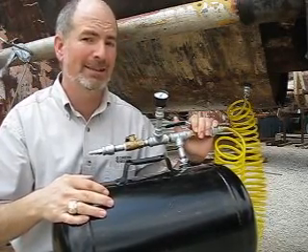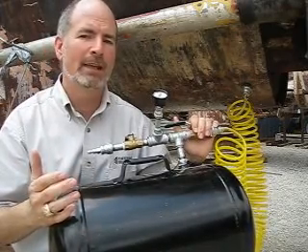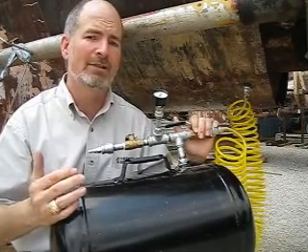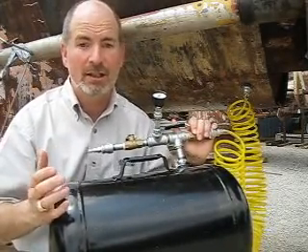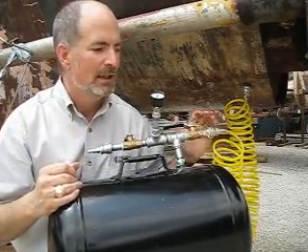Today we're talking about testing two-ply testable bellows. A lot of plants, chemical plants, refineries, power plants, have bellows that have two-ply. That's a redundant system so that if a ply fails, they don't have to worry about it. They got an extra ply. But most plants don't actually go to the trouble of testing those two-ply testable bellows. I'm going to talk about how to do that today in this video.